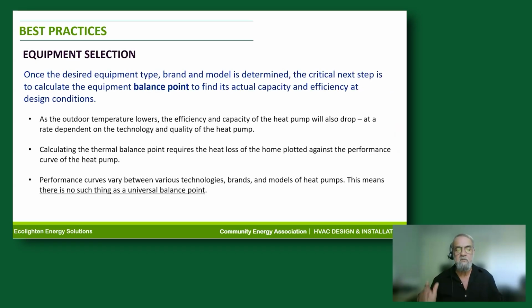Okay, you've gone through all that. You've selected the equipment. The next thing is the balance point, and I can't understate the importance of a balance point. Without the balance point, you're kind of flying blind in terms of what equipment is going to do for you at design conditions, not nominal capacity and efficiency, but at those winter temperatures that you're going to be designing for, or at those summer temperatures that you're going to be designing for. The balance point will tell you that, and will help you determine which equipment, which model, which size of your choice you're going to use.